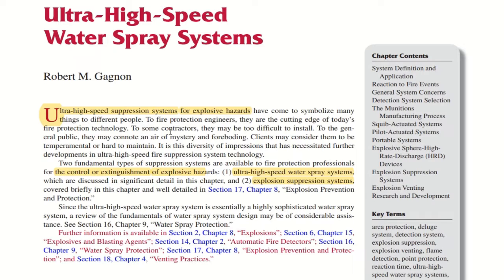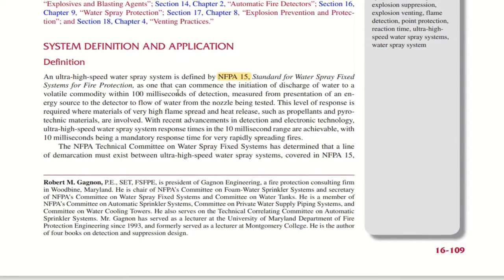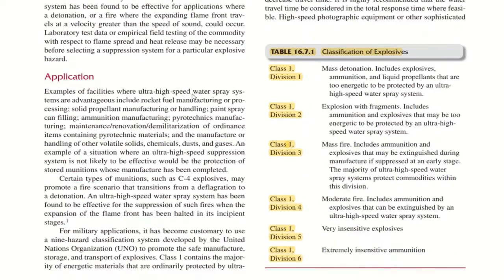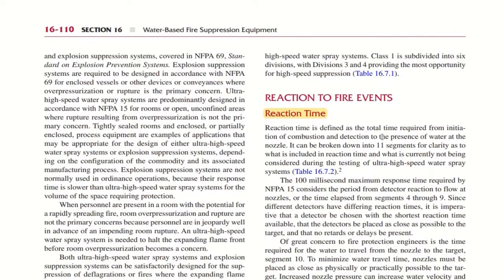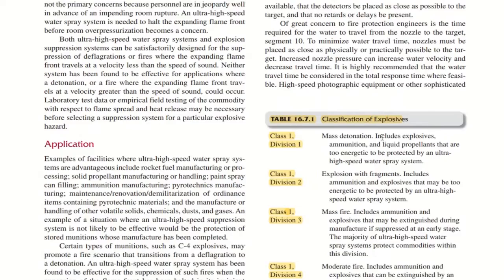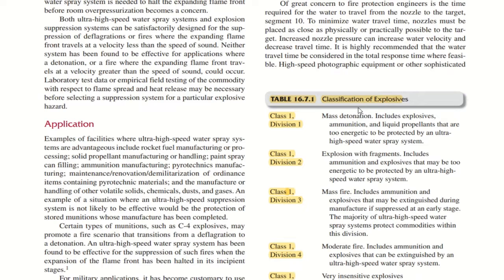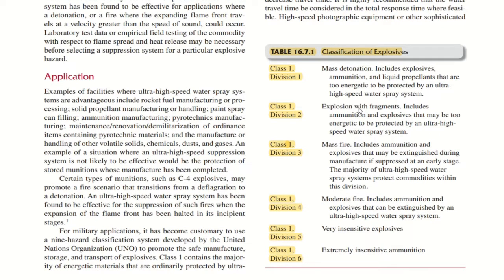Ultra high speed water spray systems, they have mentioned two fundamental types of suppression systems available to fire protection professionals for the control or extinguishment of explosive hazards. One is ultra high speed water spray systems and the other is explosion suppression systems. Ultra high speed water spray systems are defined by NFPA 15, which is the standard for water spray fixed systems for fire protection. They are showing the reaction time of these ultra high speed systems, and this is a very important table. They might definitely ask in the examination.